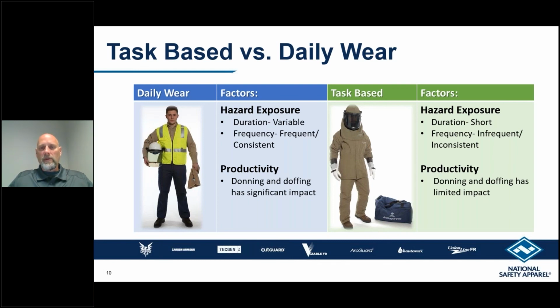Typically anything above Category 2, which requires something that looks like the beekeeper's suit on the right there, is not something people are going to wear all day, every day. That's task-based. It's also something people don't get into very frequently, and they don't spend much time in it. So you'll see Cat 3 and Cat 4 more often as task-based, and Cat 1 and Cat 2 many times as daily wear, but you will also see those as task-based as well if workers don't spend much time at all in arc flash hazard situations.